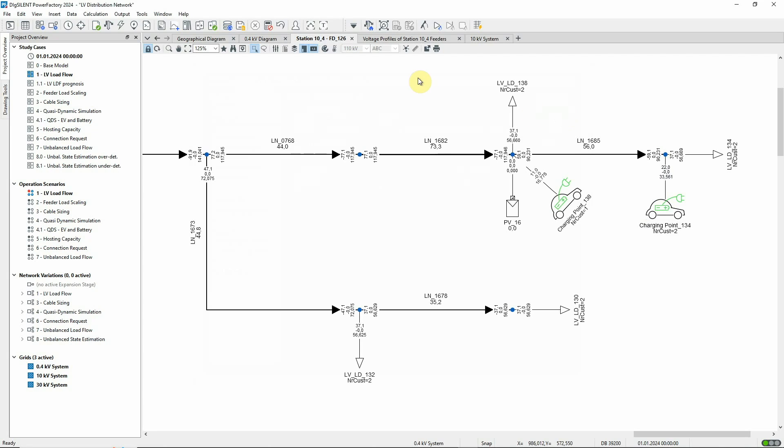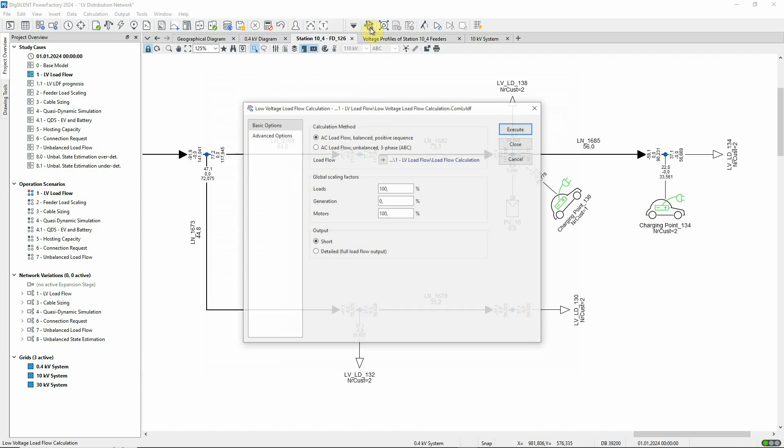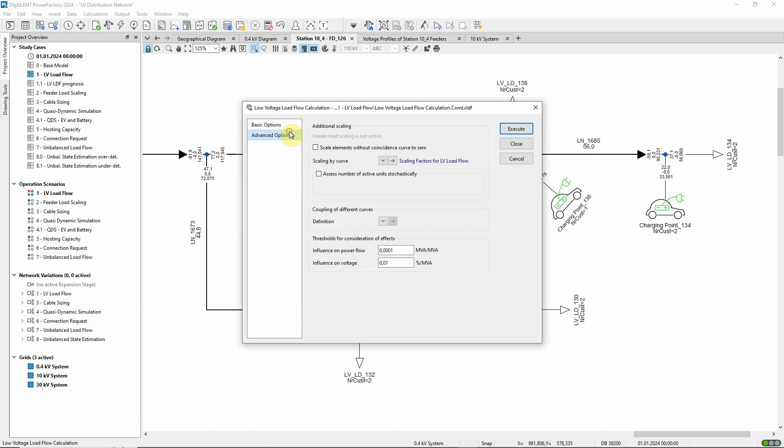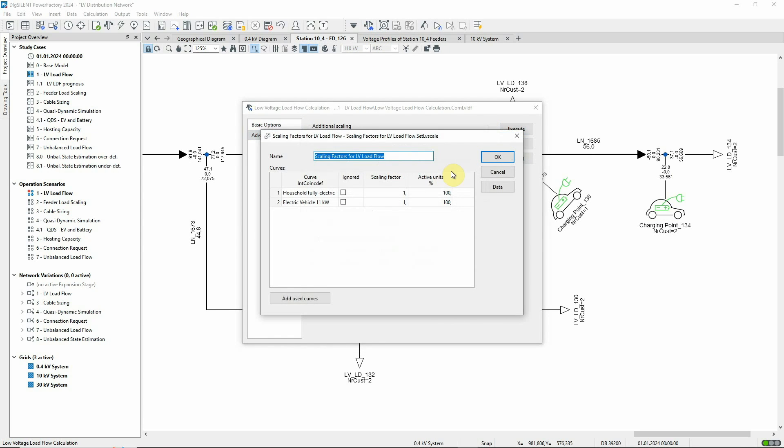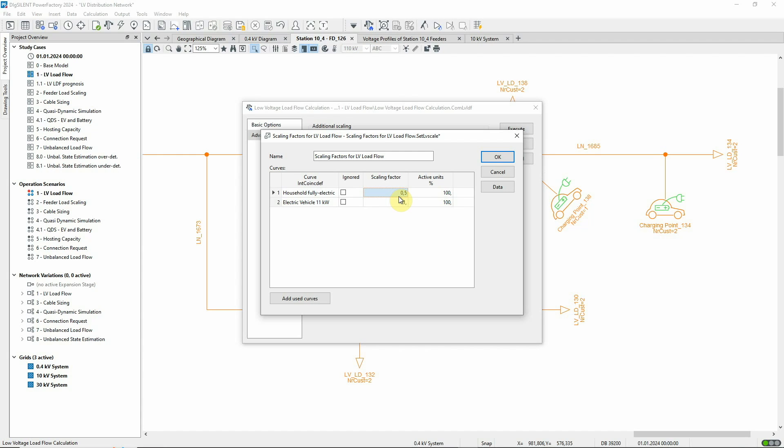Returning to the command dialog, we'll look again at the scaling factors table. Let's set the scaling factor for the household loads back to 0.5. It should be noted that these values are operational data and so will be stored in the operation scenario if one is active. This means that combinations of scaling factors for different coincidence curves can be quickly reconfigured by using sets of operation scenarios.